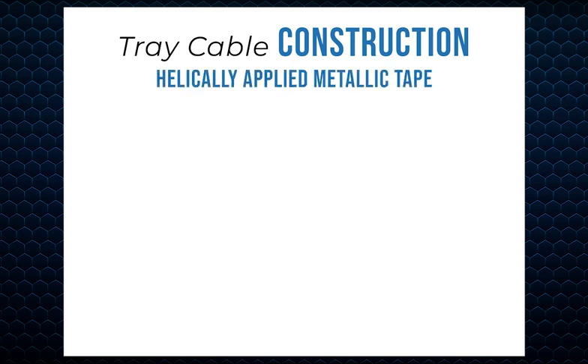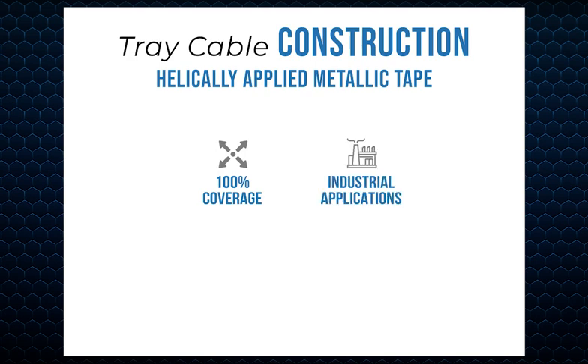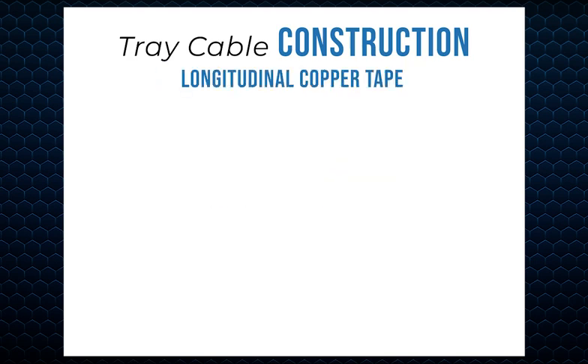Helically applied metallic tape shielding is wrapped around the cable core with a specified overlap to provide 100% coverage. This is the common shielding method for industrial applications. Longitudinal copper tape shielding is typically applied down the length of the cable with a corrugated metallic tape to provide both flexibility and added physical protection. This type of shielding is more common in utility substations.